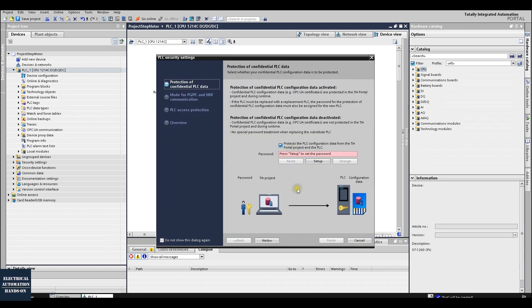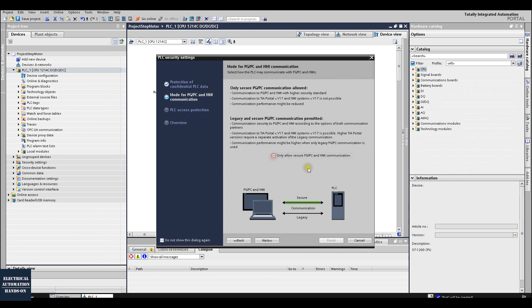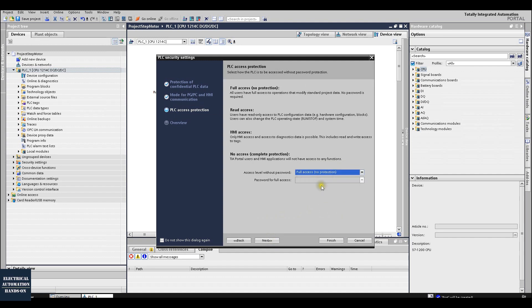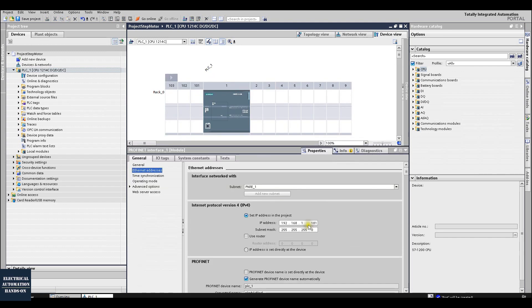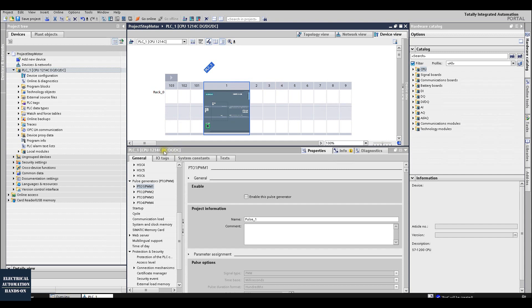These three DCs mean: the first DC is the power supply of this PLC; the second DC is the digital input — typically 24V for Siemens PLC; and the third DC for the output means this is a transistor output, typically 24V. We will use the TO (technology object) to configure our pulse output, which can run as our axis driver. It's very convenient. So we select Motion Control and then 'TO_PositioningAxis'. I'll select Automatic.